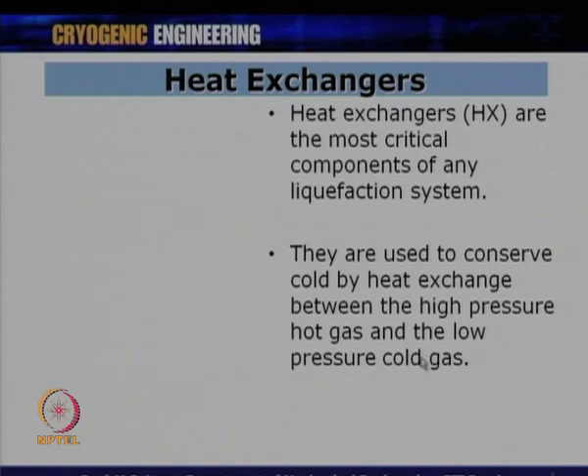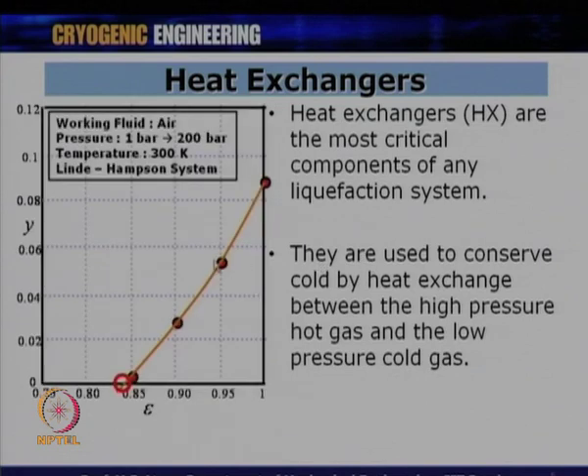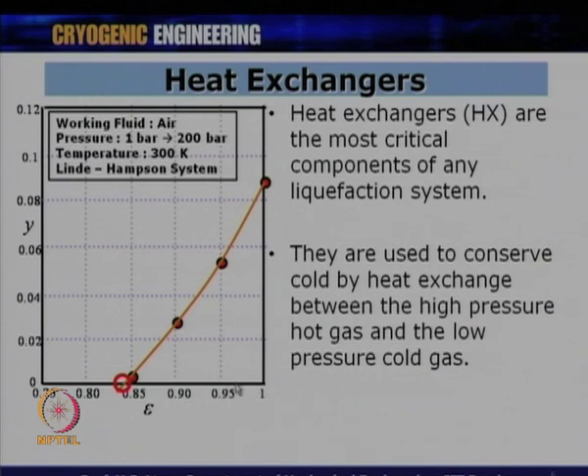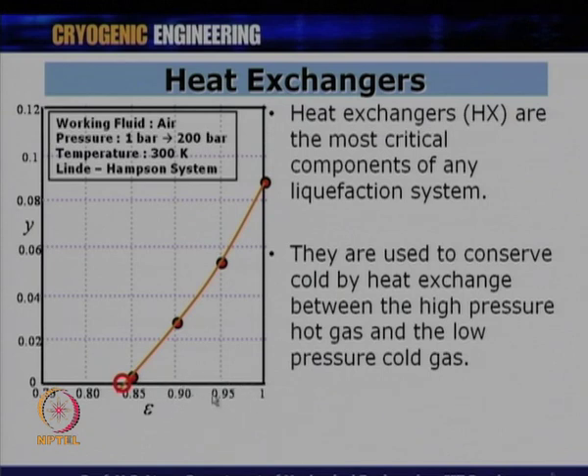Heat exchangers are used to conserve cold by heat exchange between the high-pressure hot gas and the low-pressure cold gas. This graph shows the variation in yield y with the effectiveness ε. If ε is 100%, you get the highest yield of around 0.09. As ε drops from 100% to 95% to 90%, the yield comes down. If ε is less than 85%, the yield is absolutely zero.